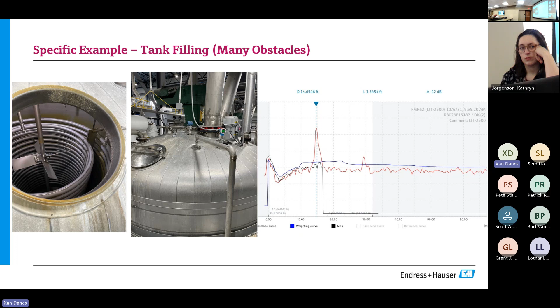In this case, we happen to have a flange installed directly in the middle of those two. This was an application that frankly probably wouldn't have been possible to install from above without this high frequency radar. So even with all that internal geometry, I have a relatively flat baseline with one strong peak, and that strong peak coincides with our level.